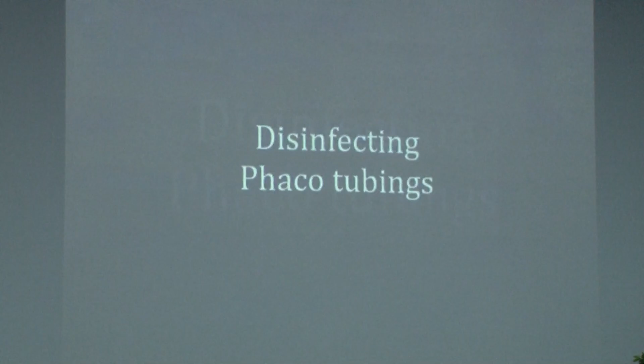Using a high flow gun is very important, but ensure you also fit in a filter like this, a nano filter, which makes the air purified, and this would help you to disinfect and remove the moisture from hollow tubings as shown here. So this is very useful if you're reprocessing your instruments immediately, not allowing adequate time for them to get air dried. So here you could see how the moisture is being let out of the phaco tubings immediately using the air gun.